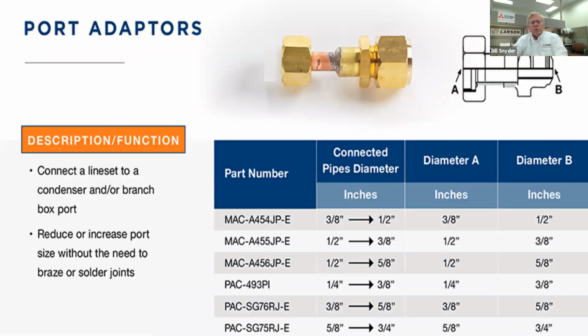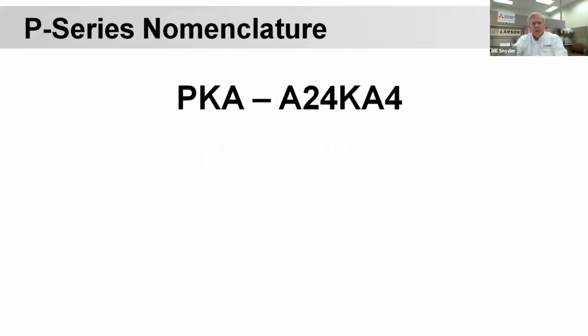On the outdoor units, the MXZs come with multiple ports. Some of them, like a 5C 42, have 5 ports. On that, they're not all 1/4 and 3/8. They might be 1/2 inch and 3/8, or 1/2 and 5/8. So there are port adapters that you can put on there, and there's a sheet that all of our branches have available that will show Mitsubishi's part number for those ports, and the JB number equivalent that we would have available.